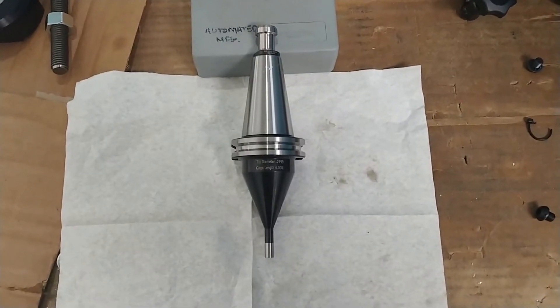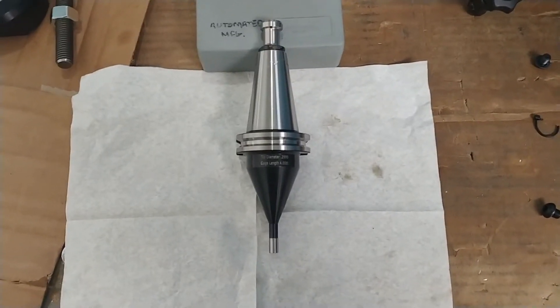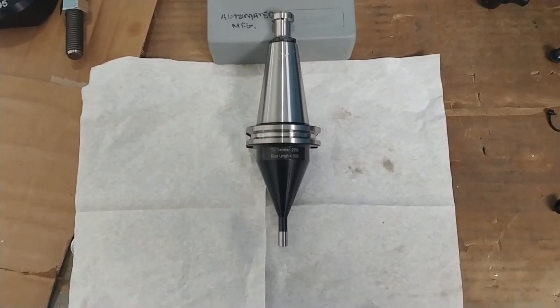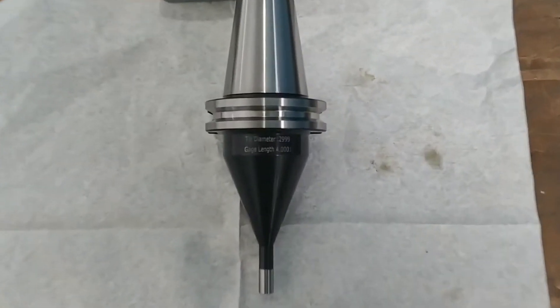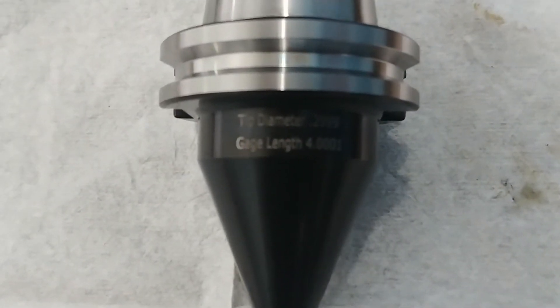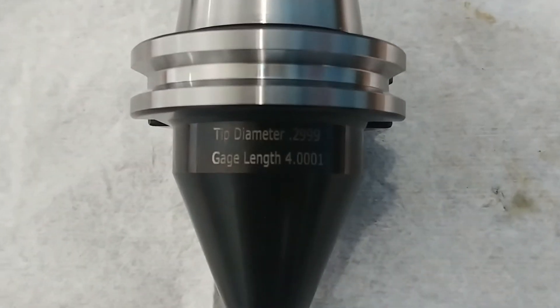To calibrate a laser toolsetter, you must run the calibration program using a master tool with a known length and a known diameter.